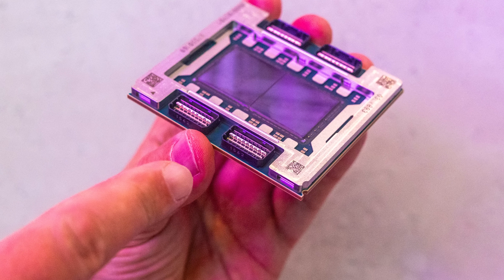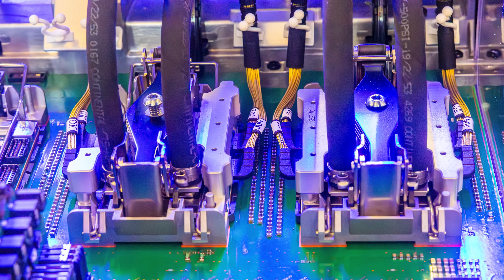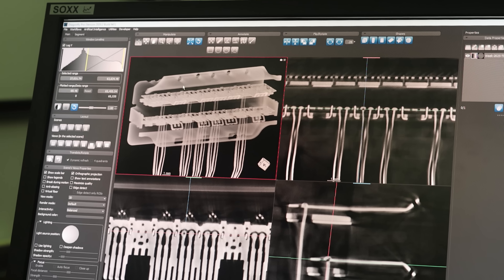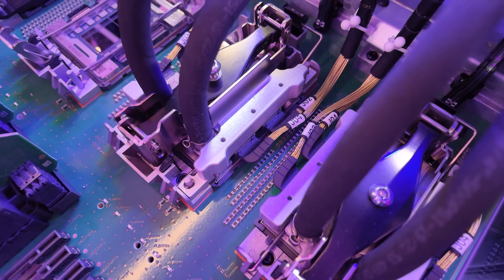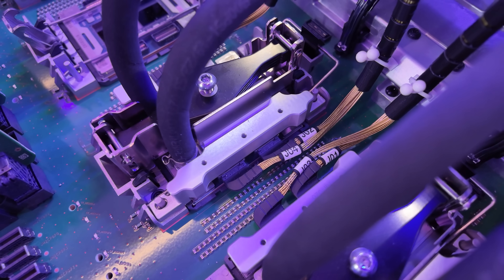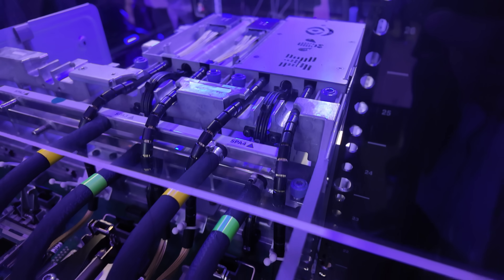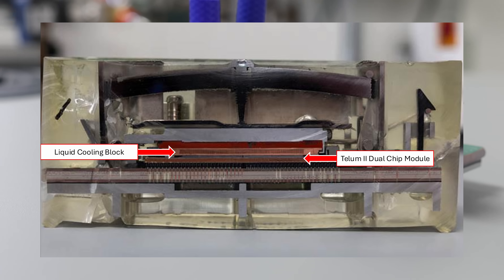The headers on top of the CPU package are SMP cables. These SMP cables allow each processor to connect to other processors in the mainframe. We got to see some amazing tools the team had for looking at cross sections of these connectors, where they can see one wire that is not connected without even opening up the connector. Cooling these processors is done via liquid cooling also at the top of the chip, but something different versus traditional server processors is that the liquid cooling here is a lot more complex. First off, the liquid cooling now uses a glycol mixture instead of just distilled water, which is a change from previous generations.